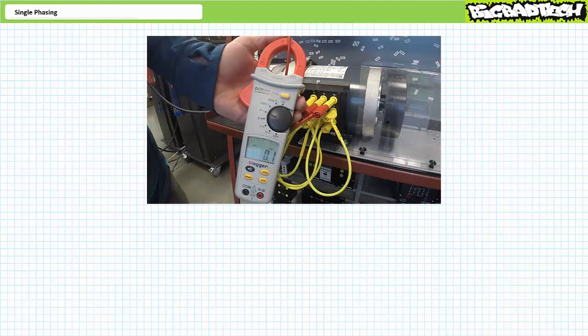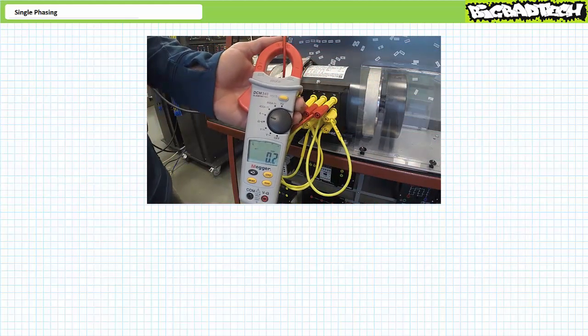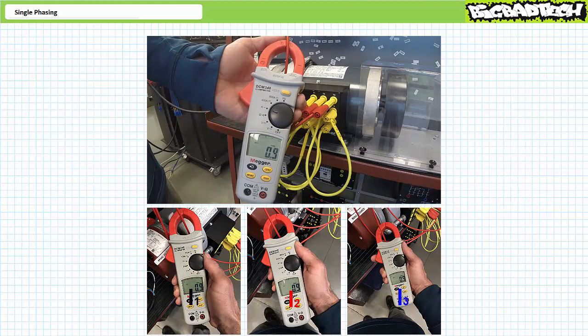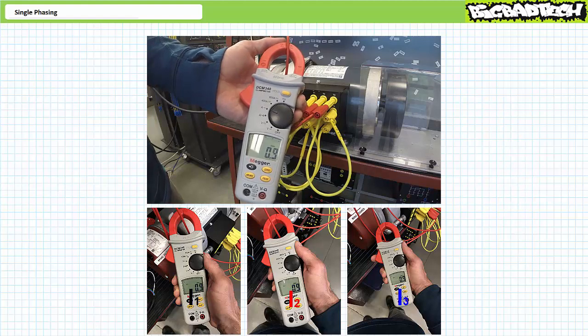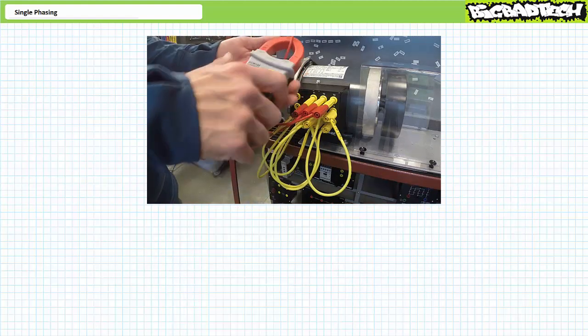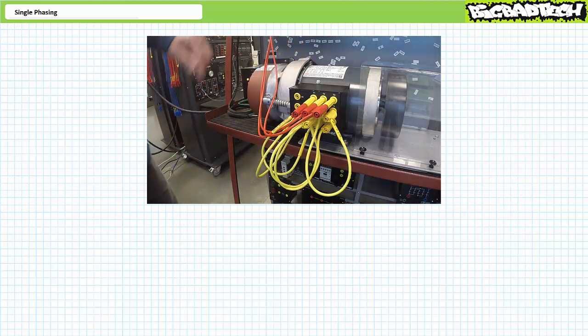Here's an example of a lightly loaded one-third horsepower motor. We use a clamp-on ammeter to measure current in normal operation and again while being single phased. In normal operation when energized, the motor experiences a brief surge of inrush and current stabilizes at 0.9 amps, or 900 milliamps. This motor's rated current is 1.6 amps, and in the lightly loaded condition, it draws much less than rated current and sounds like a regular motor.